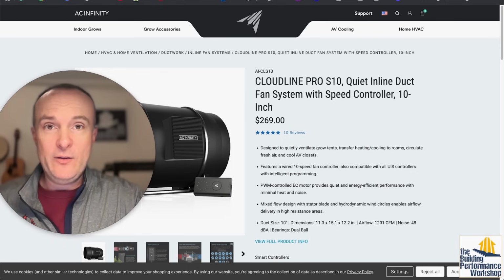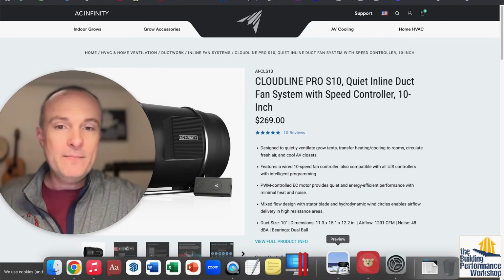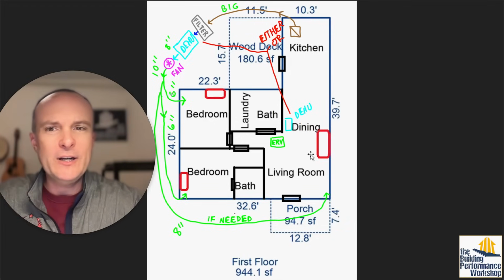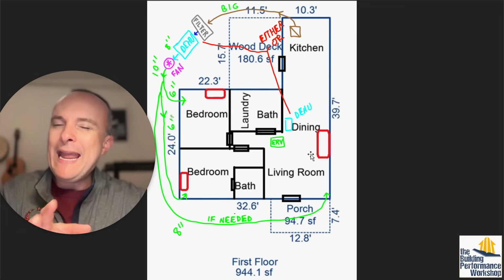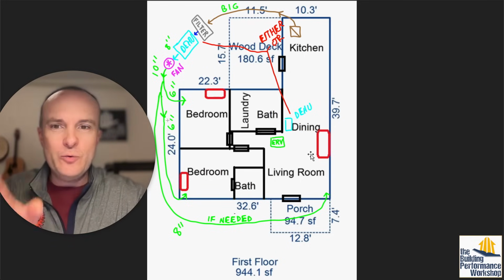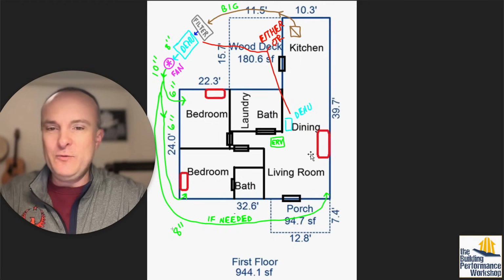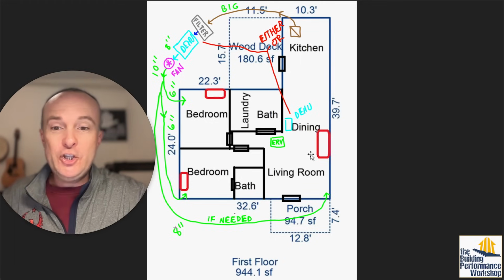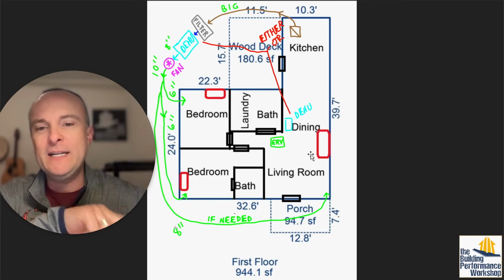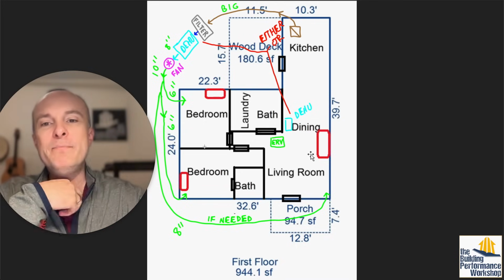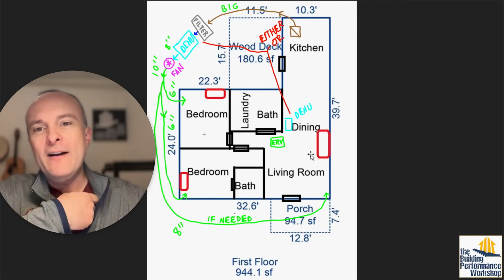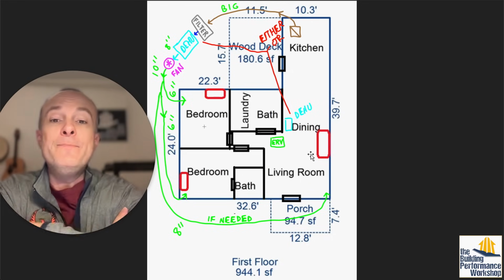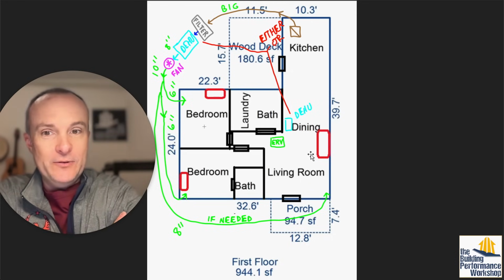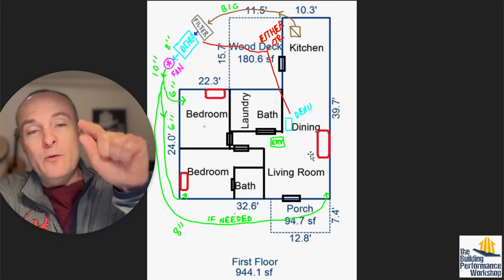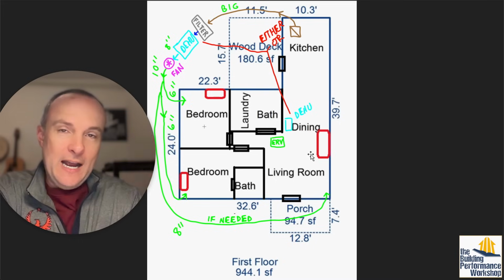For another reason, looking at this map, we're delivering air through an 8-inch duct, a 6-inch, and another 6-inch. A 6-inch duct is about 28 square inches, we'll call it 25. So that's 25 square inches, 25 square inches, and 50 square inches—basically 1, 1, 2 parts, meaning 2 parts of air delivered to the living room and 1 part to each bedroom. We can't deliver more than 75 CFM into each bedroom, or we won't be able to get the air back out under the door undercut.